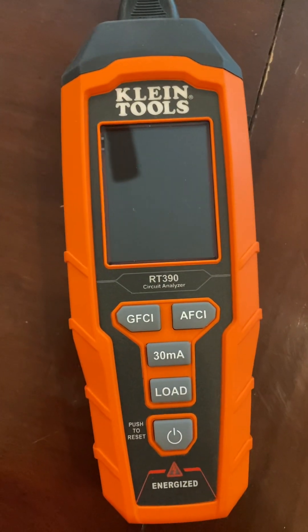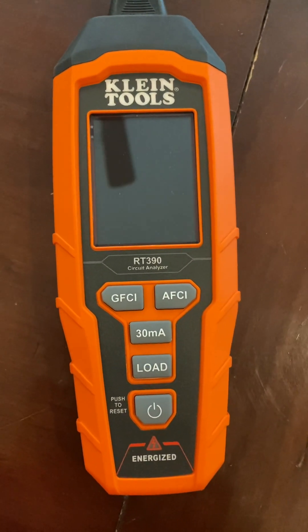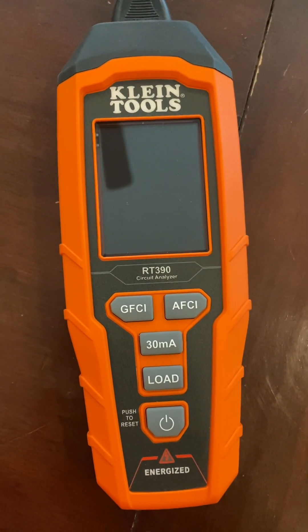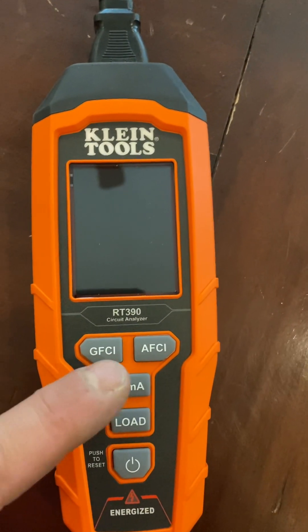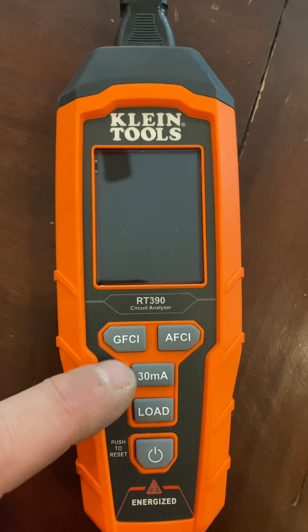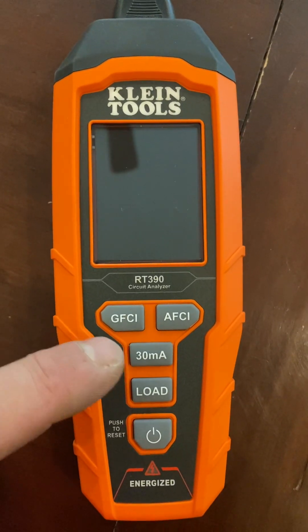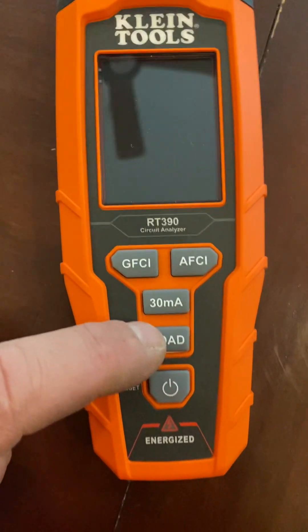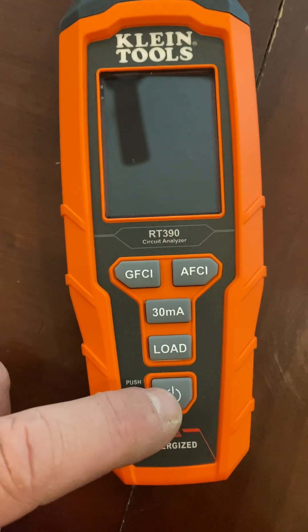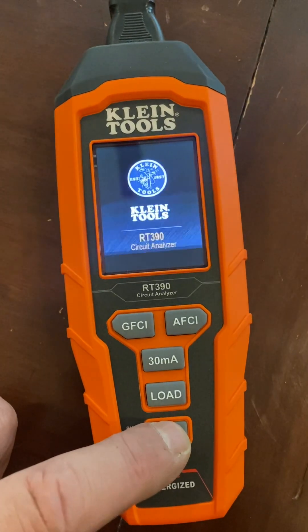A mini review of my Klein circuit analyzer that just showed up today — it's the RT390. It tests GFI, arc faults, and a 30 milliamp RCD, which is what the larger GFCI breakers use. It'll put a simulated load on it and test wiring. Let's fire it up and see how it goes.